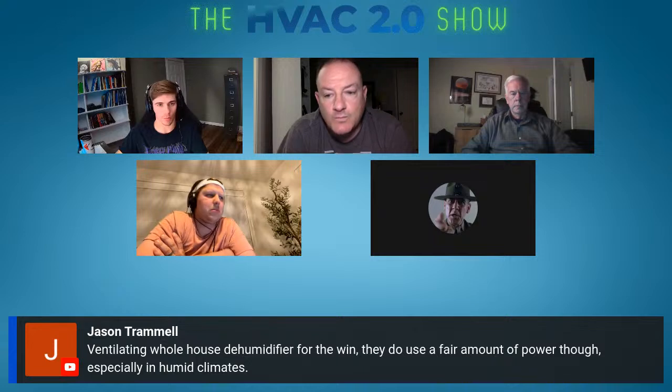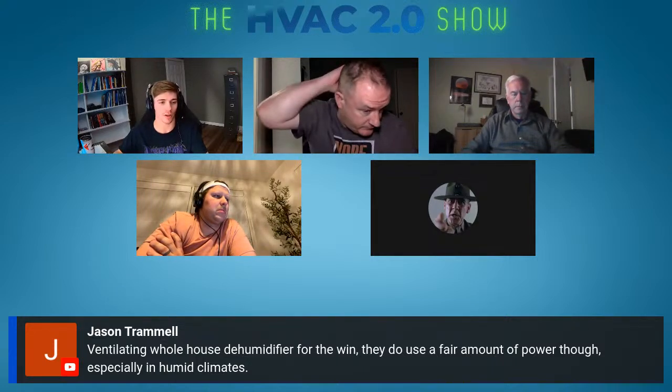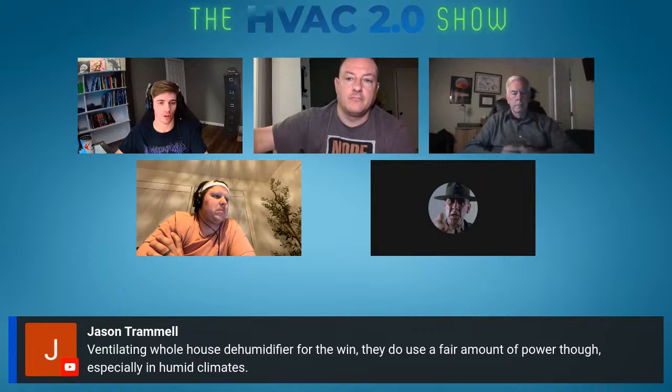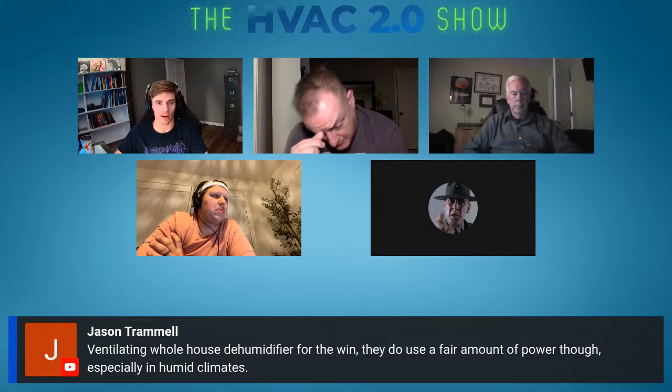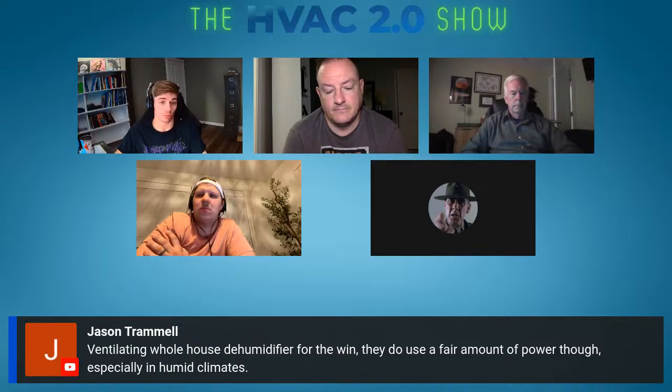You're just dealing with a lot bigger equipment, bigger coils, whereas with dehumidifiers, look at how small the coils are. To pull moisture out of air in a large house with such a small box, that's hard work. There's a reason why they tend to not last very long. It's not because manufacturers suck at their jobs and can't build good equipment. No, they build really good equipment. It's just a really difficult job to dehumidify and to keep up.